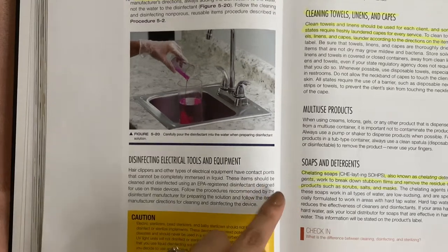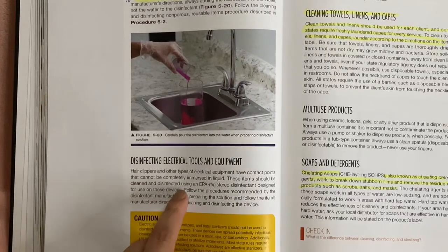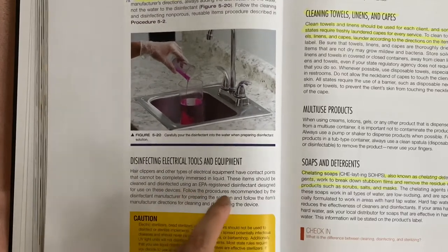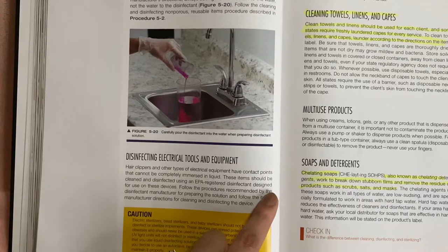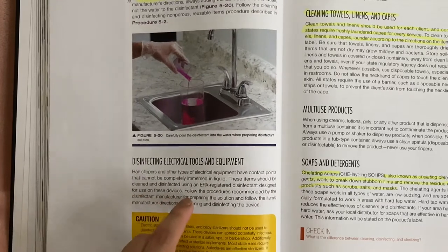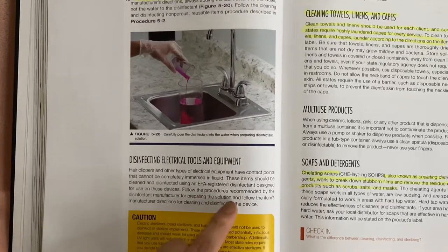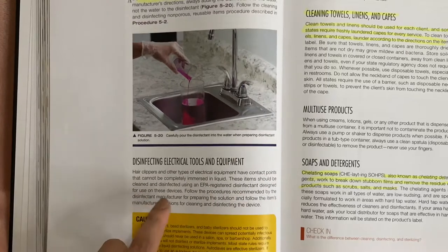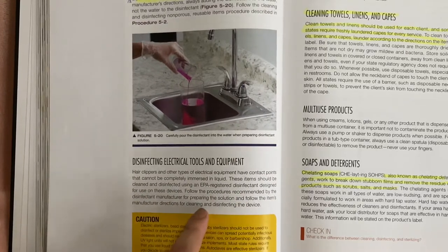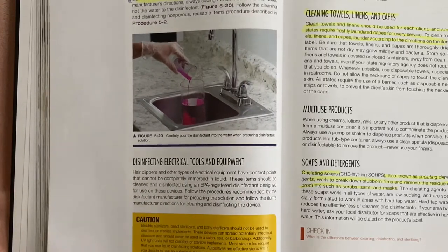These items should be cleaned and disinfected using an EPA registered disinfectant designed for the use of these devices. Follow the procedures recommended by the disinfectant manufacturer for preparing the solution, and follow the item manufacturer's directions for cleaning and disinfecting the device.